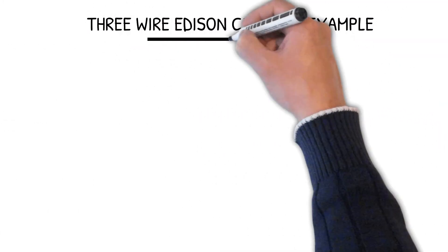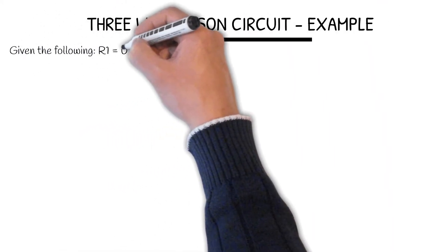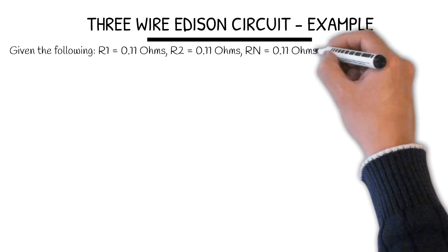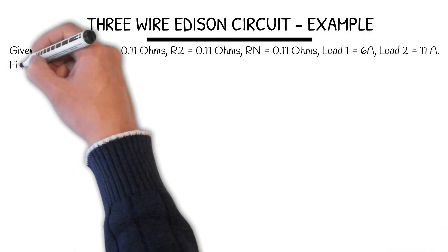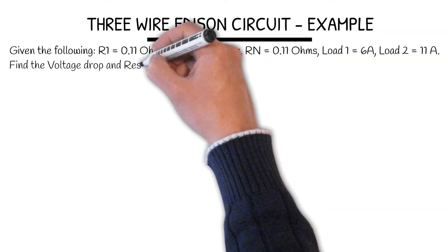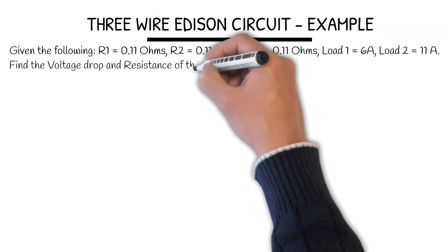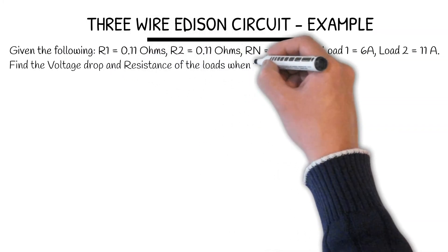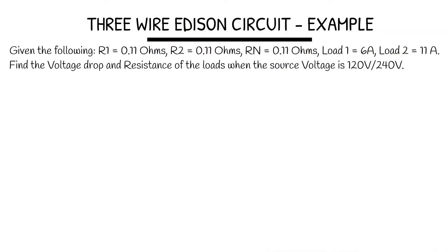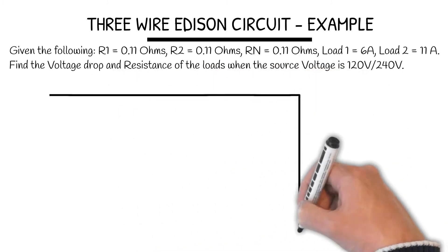3-Wire Edison Circuit Example. Given the following: if all the resistors are 0.11 ohms, load one is 6 amps, load two is 11 amps, we want to find the volt drops and resistance of the load when the source voltage is 120/240 volts.